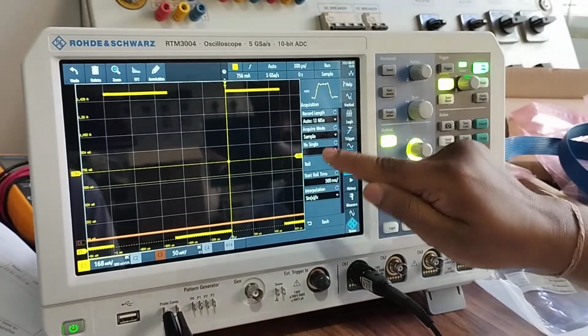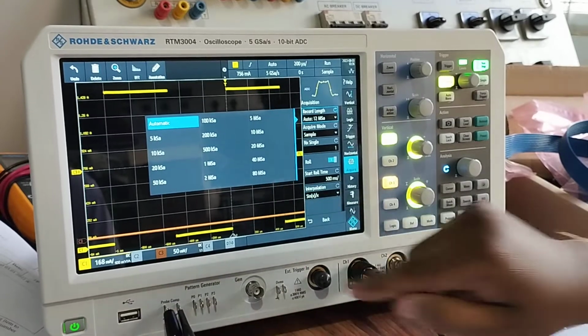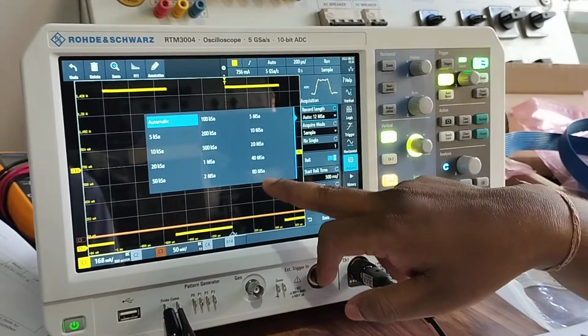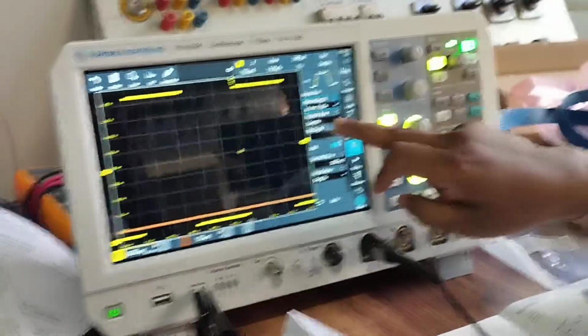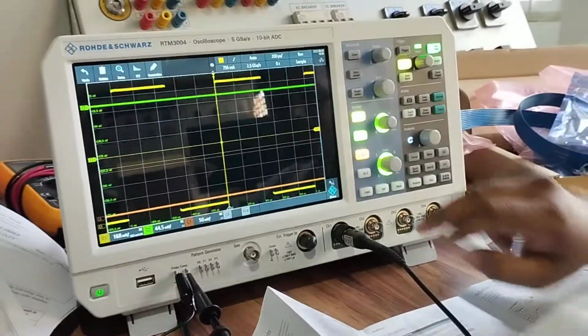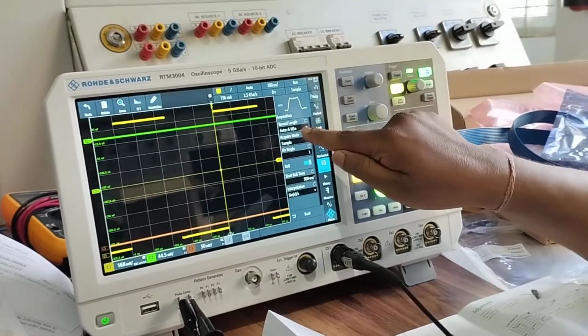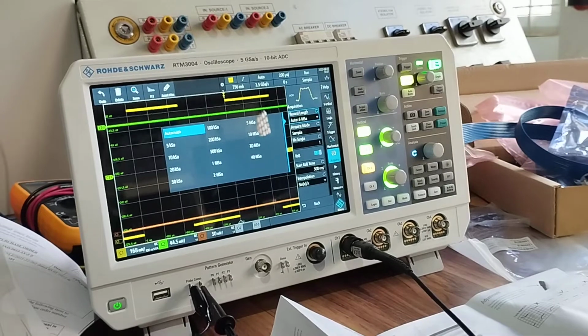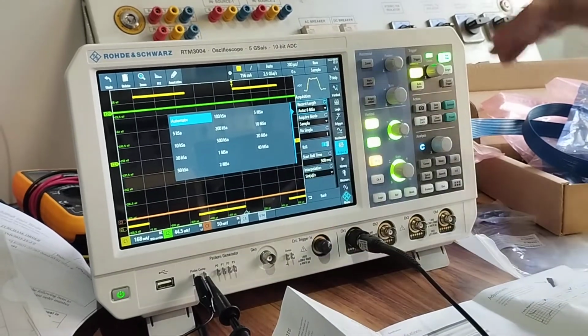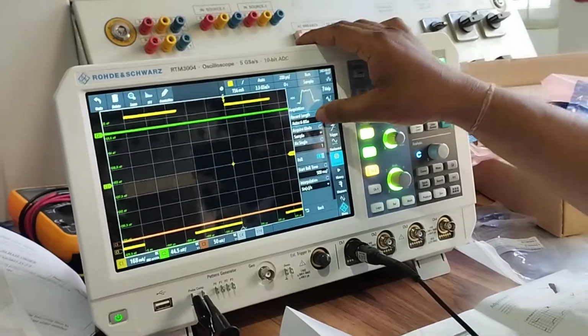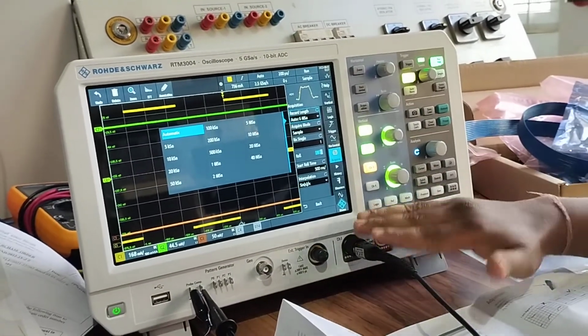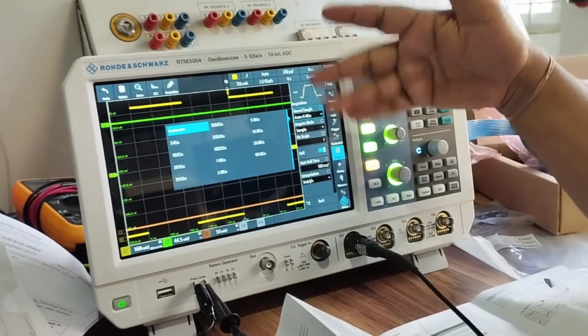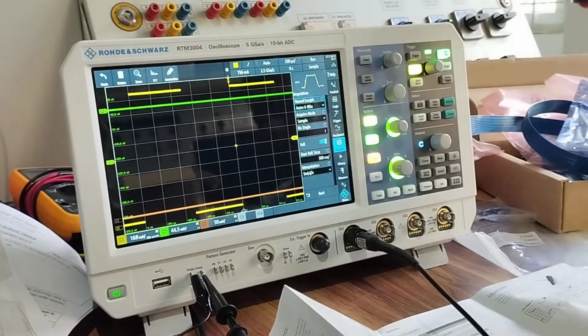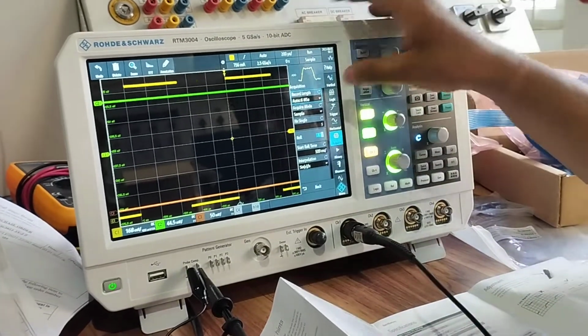Here I also want to show the acquisition memory. In this RTM we have a maximum memory of 80 million points. If channels 1 and 3 are there, you can do a memory of up to 80 million points. If I switch on channel 2, the memory is only up to 40 million points. Actually, as per our data sheet, memory is 40 million points on each channel. Normally we select automatic, and depending upon the frequency and the sampling rate, the equipment calculates the memory by default. If you want more memory, you can select high memory. And here we have the various acquisitions, which I can show you from the desktop.